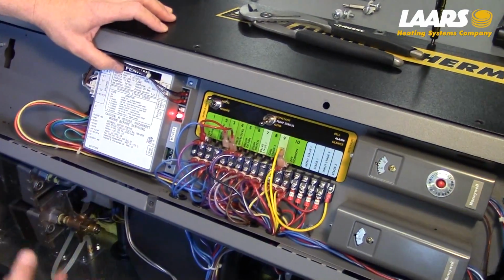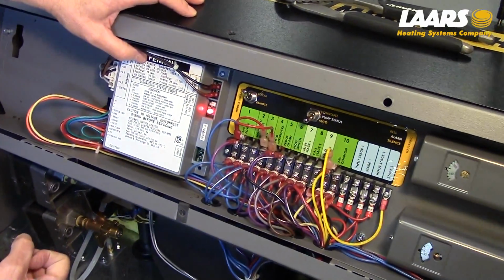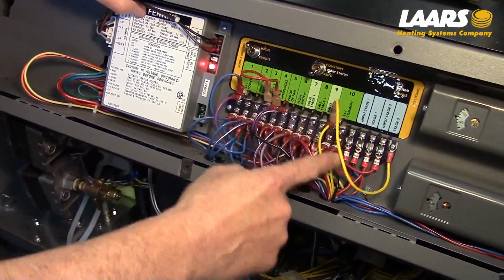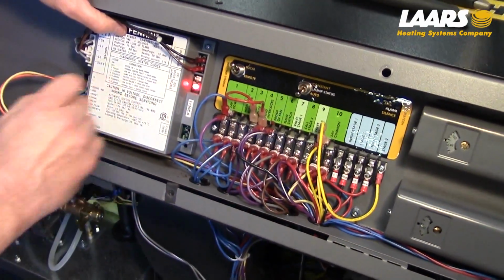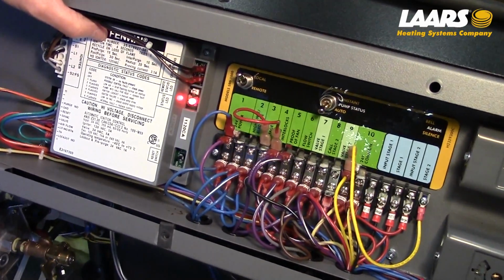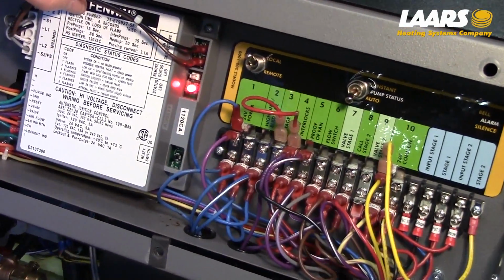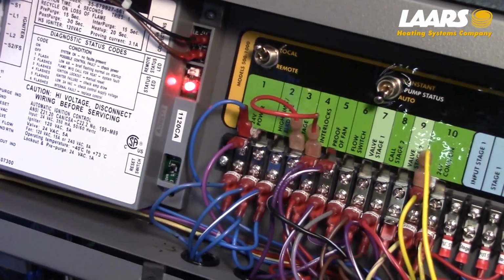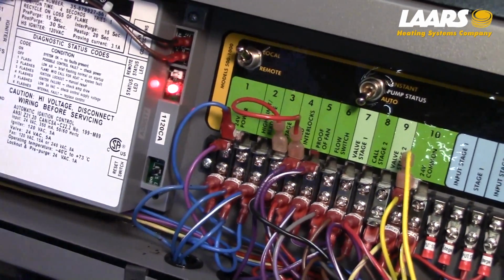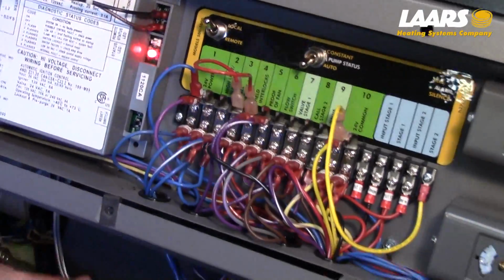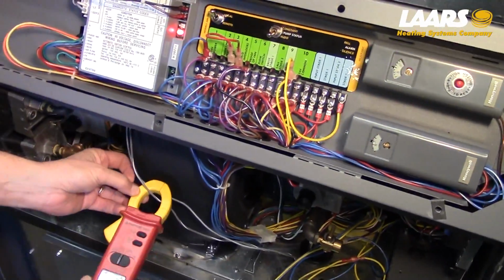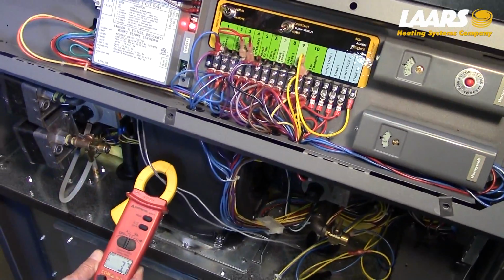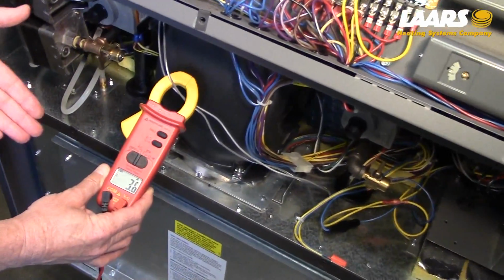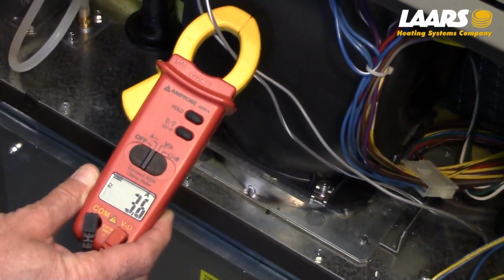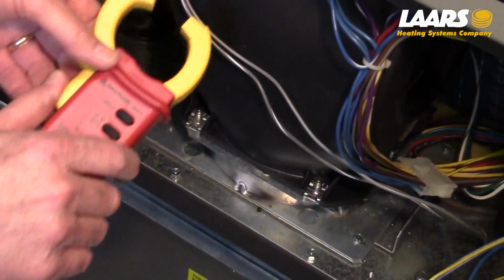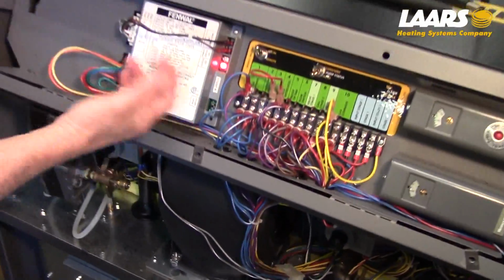Once the fan comes on and proves the fan, and our flow switch and everything else in the safety chain is made, we'll see a single flash. And now with an amp probe, I can put my amp probe on either one of the wires, and we'll see that we're looking, again, 3.4 or greater for amperage, okay? If we don't, that means you have a bad igniter, and that's why we went into the ignition fault.